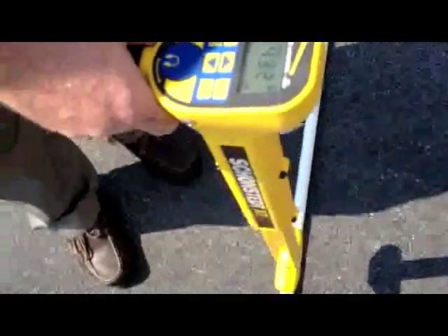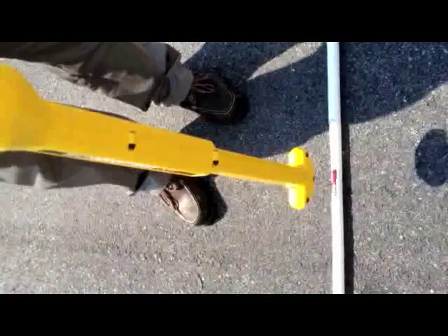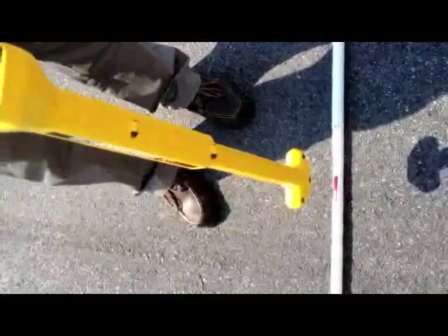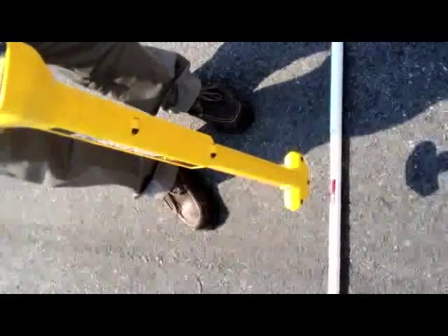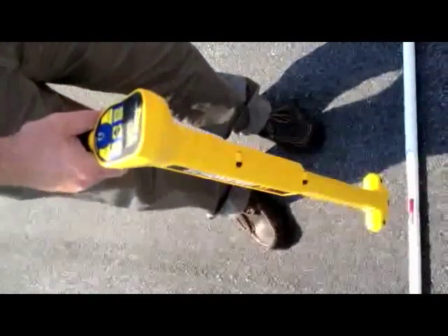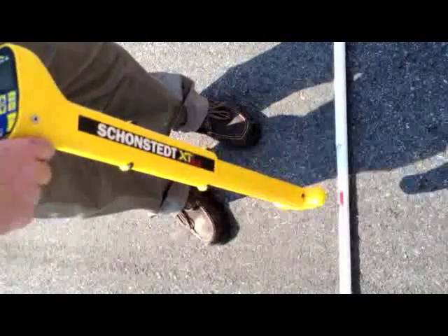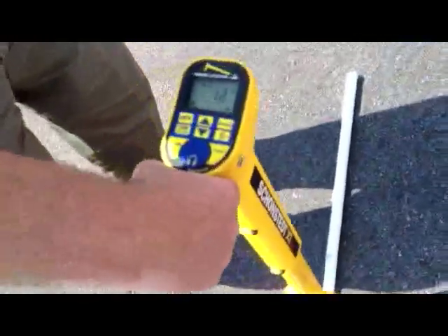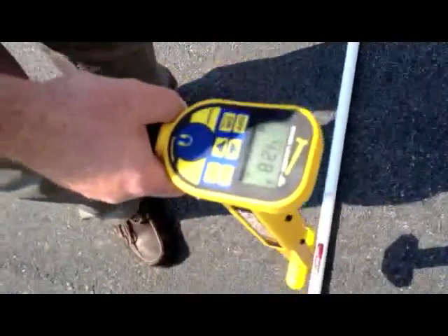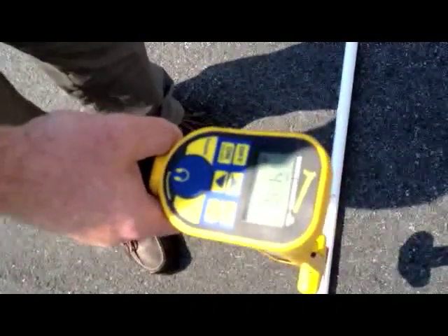To demonstrate determining the depth of where the beacon or camera is positioned, the transmitter within the camera, I need to be square or in line with the arrowhead tips with the beacon. Notice this, if I take the instrument out of square with the arrowhead tips, we go back to a null. In order to get a depth reading out of the instrument, you would want to be in this orientation where you get the highest peak directly over it.